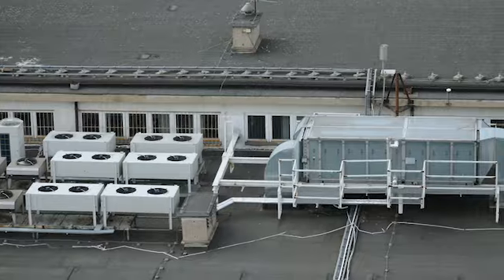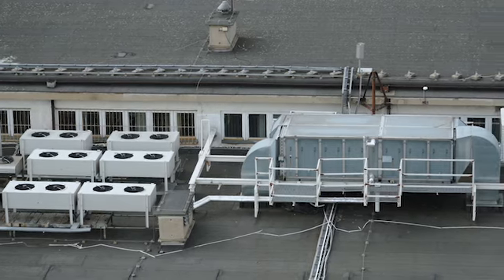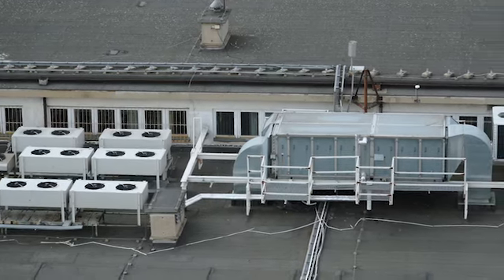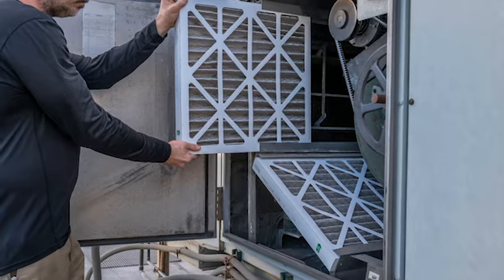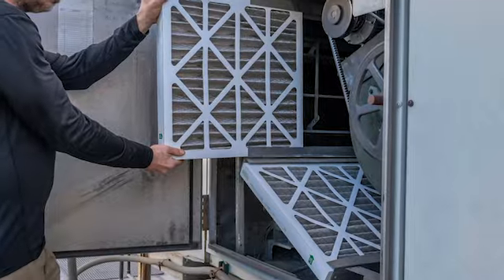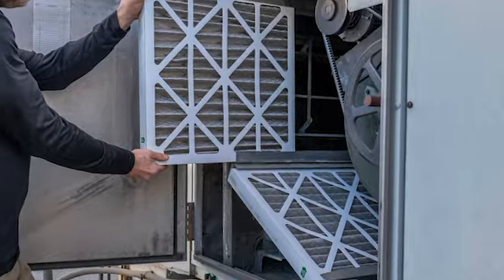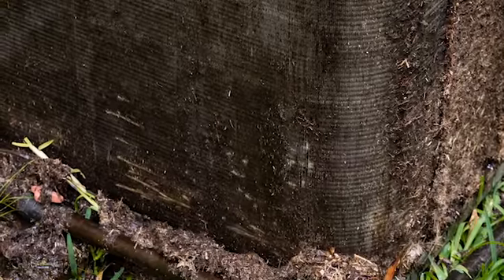How can facility managers balance energy efficiency with maintaining optimal indoor air quality during the winter season? Typically, you should have a minimum outdoor air setting on your outdoor air dampers. You want to make sure that those minimum airs are set properly and functioning the way they should. The other part is making sure that you have clean filters in your air handling units, and the mixing boxes are vacuumed out of bugs and leaves and all the other debris that accumulates over the summer months.